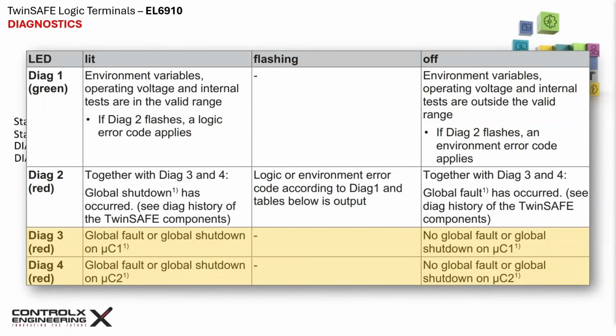Note that a global shutdown temporarily disables the TwinSAFE controller. This error can be reset by switching the power to the terminal. However, a global fault permanently disables the TwinSAFE controller, meaning that it has to be replaced.